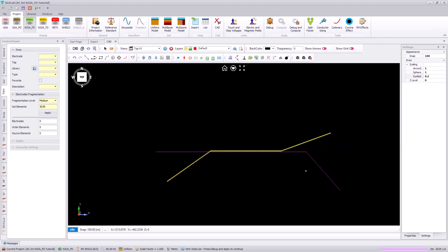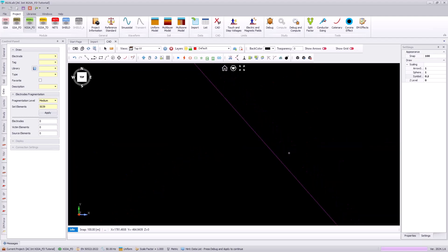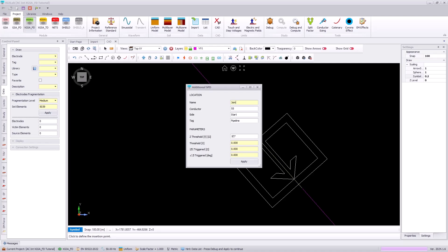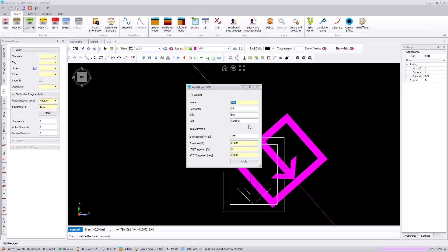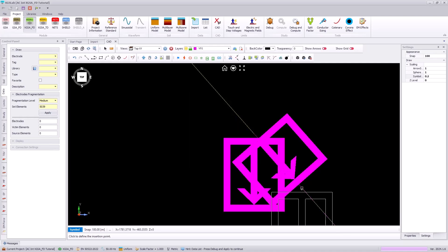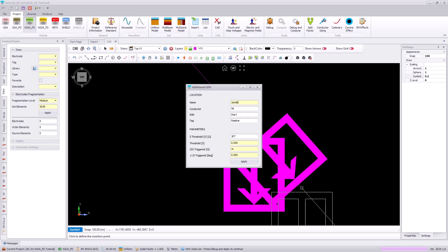Now we'll go to the right side of our pipeline and insert a similar transverse and longitudinal impedance. We select the longitudinal impedance symbol and enter it as Joint B, specifying the same 650 volt threshold with a 0.001 ohm impedance for that longitudinal impedance. We will then insert a transverse impedance called Joint B up, and following the tutorial documentation we will use the 70 volt threshold but now a 5 ohm impedance once triggered. We'll do the same thing below this joint, specifying 70 volts with a 5 ohm impedance.